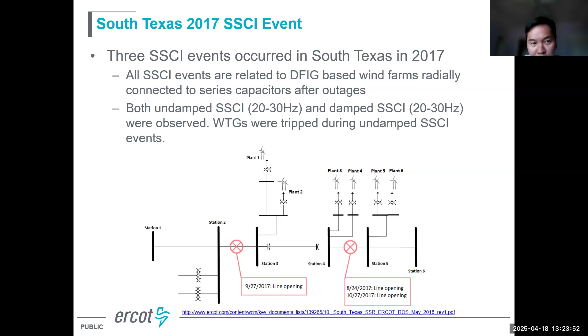They tripped, but this is not good for us because, as I said, all the wind farms here had simulated the SSR, and the simulation in PSCAD showed no issue, but in reality, we had issues. Later we coordinated with the plant owners. Basically, all these wind farms have an SSR mitigation controller. I think they tried to tune the controller, and after that, it was okay until 2023.